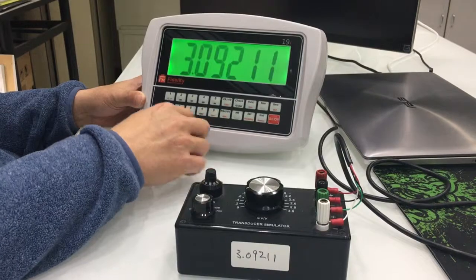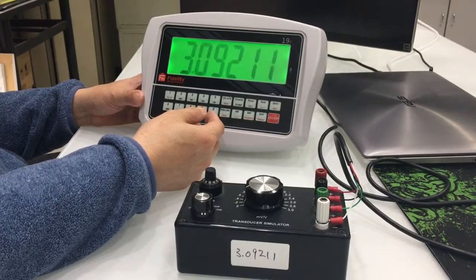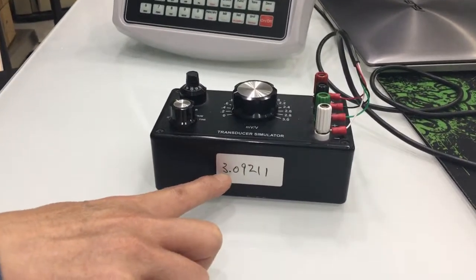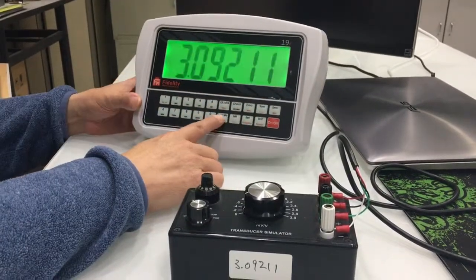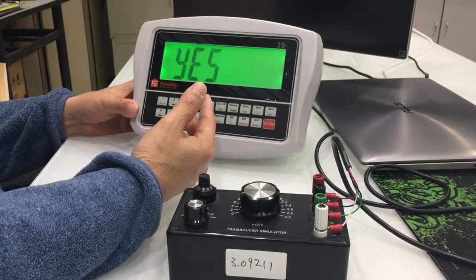Then the next step is to enter the load cell rated output. The output of this simulator is 3.09211, so I will enter the same here and then press enter to continue.